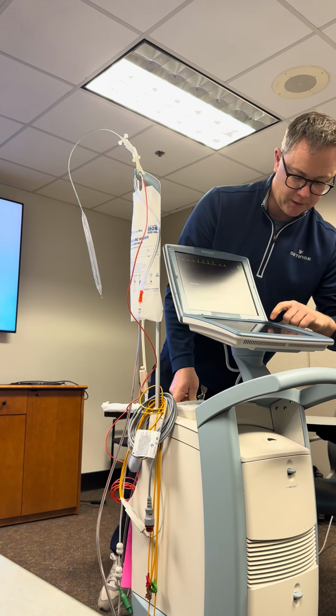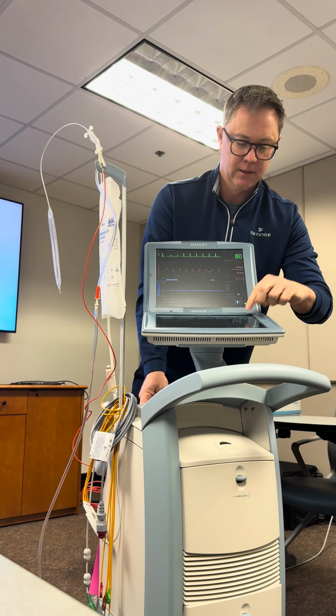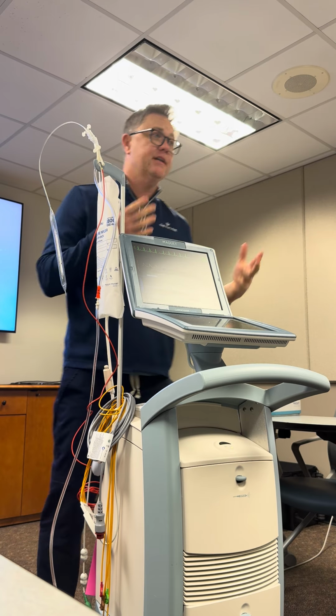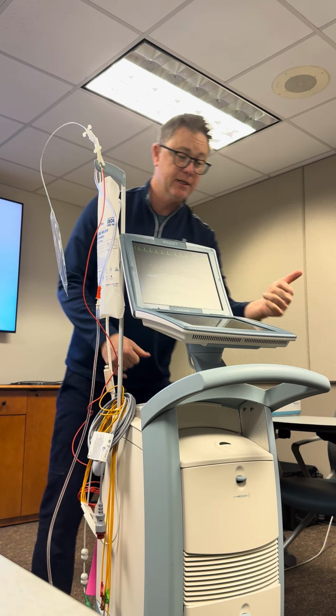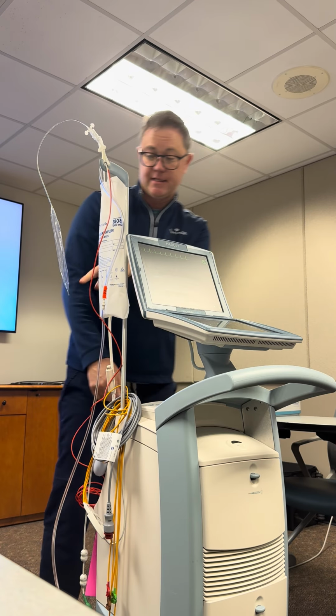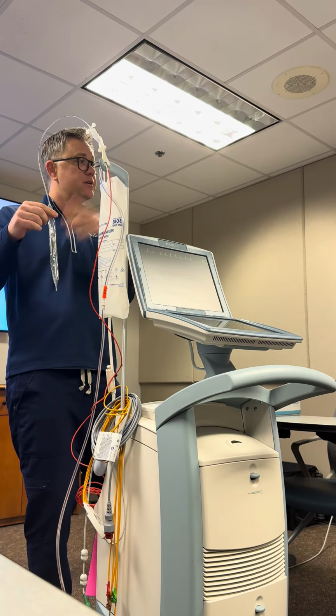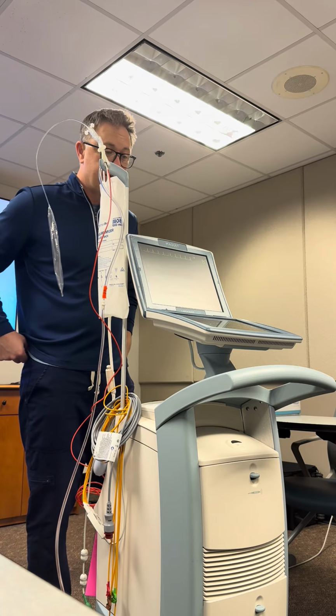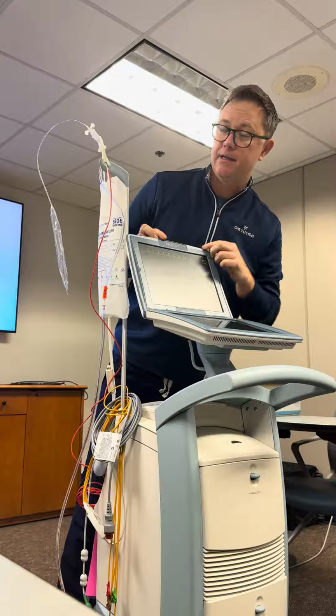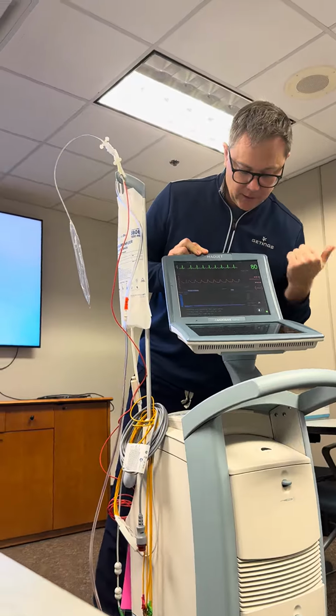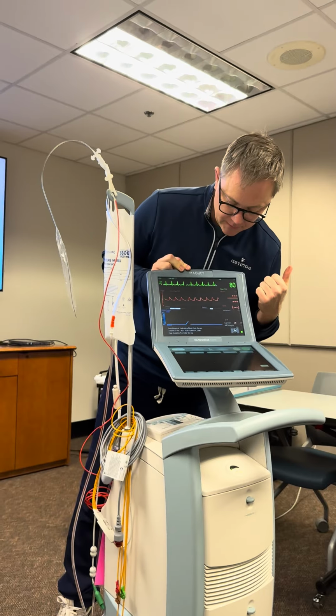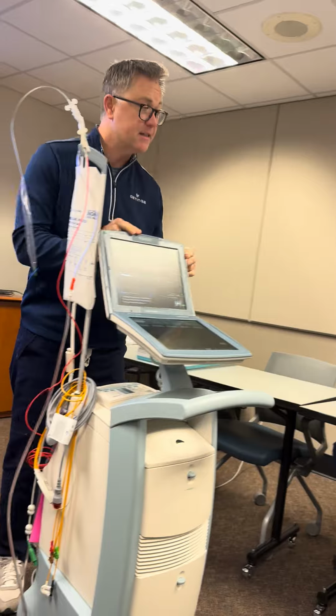To start this guy up, we're gonna hit the start button. When you hit start, it takes about 30 seconds to initialize therapy. So it's going to zero out the catheter. It's gonna size the balloon catheter so it knows how much helium to shuttle back and forth. And it's gonna do a timing check. So just be aware when you start this guy up, the whole process takes roughly 30 seconds.